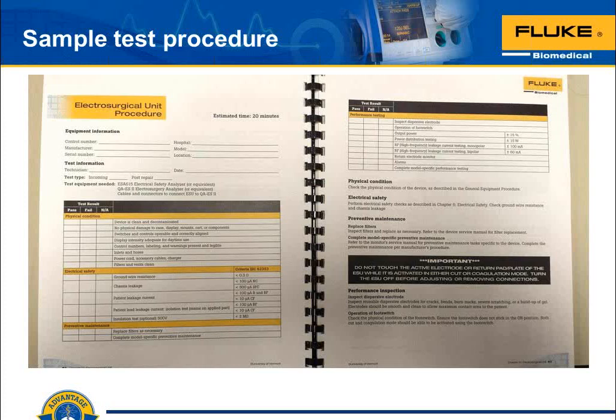So we added an inspection step to preventive maintenance. It was called open the ESU and vacuum out all the lint. Why vacuum? Because if you use compressed air and you blow it out, you're liable to blow some of that lint into edge connectors, which are going to short circuit power supplies and so forth, so you don't want to do that. So we use the vacuum. We're very careful about pulling all of the lint out of there. If we needed to use a little brush to help tease some of that out, we did. But we pulled all of that out of there, and that was part of our regular inspection procedure every 6 months on ESUs. And that stopped the burnout of our final stage amplifiers to a huge degree.